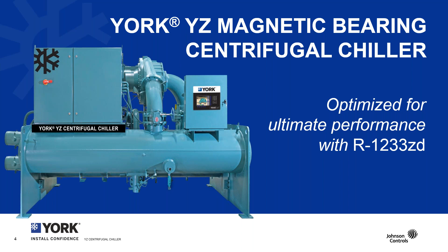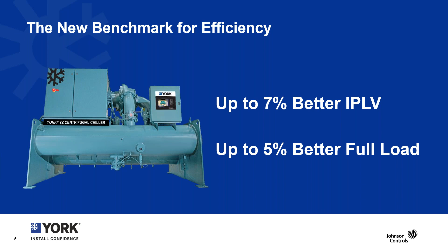And we've done just that. It is the new benchmark for efficiency. This means up to 7% improvement in IPLV part load performance and up to 5% improvement in full load performance. That's delivering IPLVs at the 0.297 levels and full loads below 0.50, as low as 0.49 kW per ton.